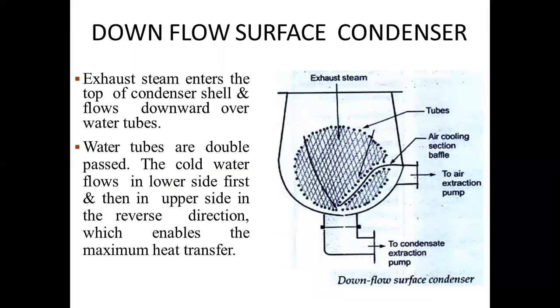Next one is downflow surface condenser. In case of downflow surface condenser, you can see there is a diagram which shows the downflow surface condenser. Here we are using a nest of pipes which can be honeycomb shaped. So here there are various tubes. Water is passed through the tubes and exhaust steam is outside the tubes.